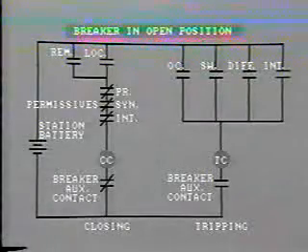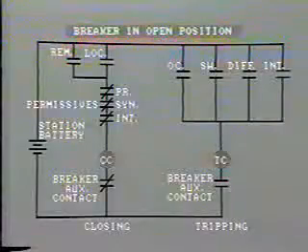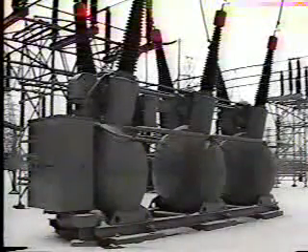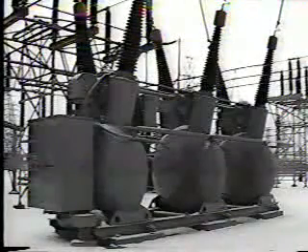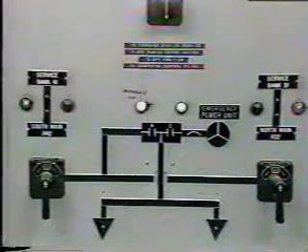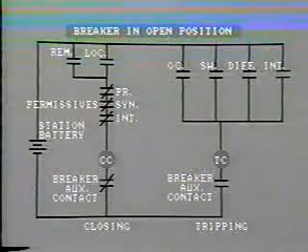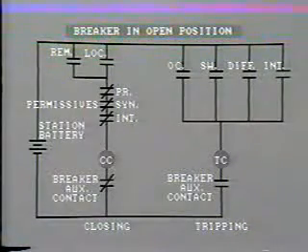Another type of diagram that you must be completely familiar with is the control circuit schematic. As we have already mentioned, circuit breaker components may be physically far apart. The closing and tripping coils are located adjacent to the breaker. The manual switching contact is a considerable distance away on the control panel. The protection relay contacts inside the relay may be in yet another location. However, from an electrical point of view, the breaker control circuit looks like this.